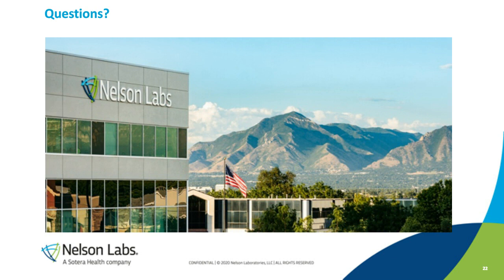Great. Okay. Our next question comes from Tuba. Hope I'm pronouncing the name correctly. How do we decide a sample size? Is there a standard for the sample size calculation? That is a good question, and the short answer is that no, there isn't really a direct standard for that. Oftentimes labs are tempted to use ISO 10993-12, which sets surface area to volume or mass to volume ratios, and that can kind of fix the sample size in terms of how much volume is needed for an analysis and so on.